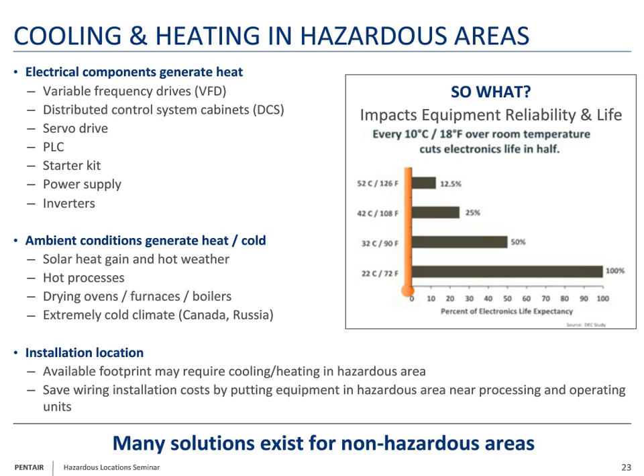In addition to that, those pieces of equipment can generate heat themselves, and the ambient conditions can generate a lot of heat. So if you put a stainless steel enclosure outdoors in a really sunny area, there's going to be a lot of solar heat gain, as well as the ambient temperature around it creating heat gain, and the temperatures can get quite hot, up to 120 degrees Fahrenheit, and you're going to want to cool that control panel to keep your equipment operating within its designed limits.